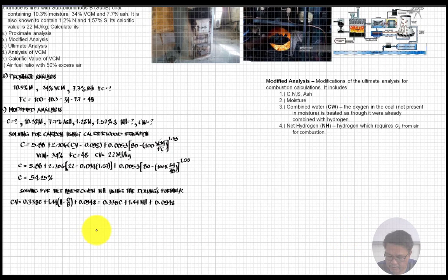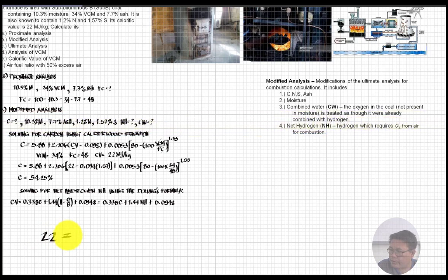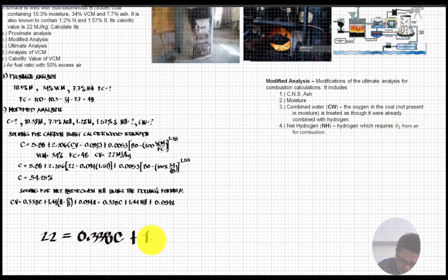Substituting the known values: the calorific value is 22 megajoules per kilogram, carbon is 54.25 percent, sulfur is 1.57 percent. So: 22 = 0.338 × 54.25 + 1.44 × (net hydrogen) + 0.094 × 1.57. We then solve for the net hydrogen from this equation.